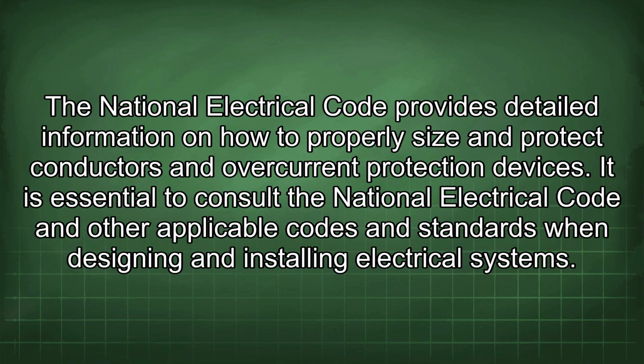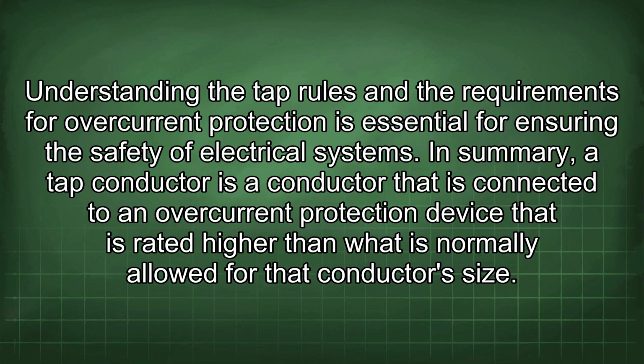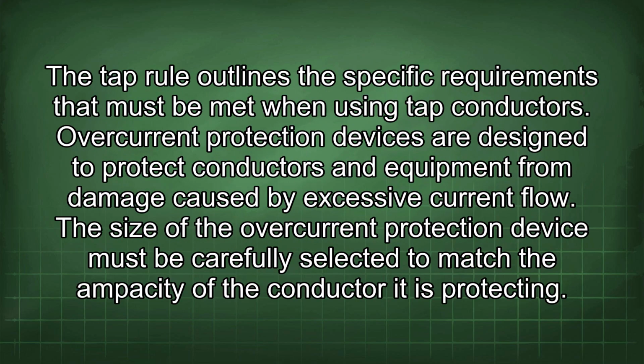The National Electrical Code provides detailed information on how to properly size and protect conductors and overcurrent protection devices. It is essential to consult the National Electrical Code and other applicable codes and standards when designing and installing electrical systems. Understanding the tap rules and the requirements for overcurrent protection is essential for ensuring the safety of electrical systems. In summary, a tap conductor is a conductor that is connected to an overcurrent protection device that is rated higher than what is normally allowed for that conductor's size. The tap rule outlines the specific requirements that must be met when using tap conductors.